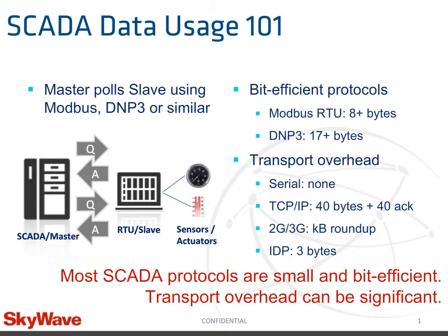It is important to note that not all SCADA transactions are just tiny chunks of data, and larger SCADA packets mean smaller overhead contribution to total usage. An example could be a historical trend report from a flow meter, so it is important to understand your application to understand how much data saving you can reap from overhead reduction.